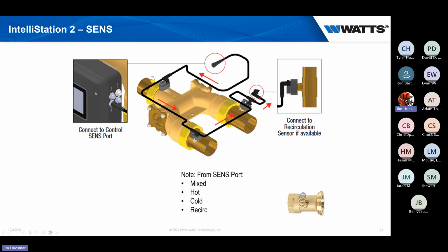What's also nice is now we have just 3, and we'll have 1 for the return, so just 4. But normally when we have 4, we'd have to consider that 8, because normally 1 is temperature and 1 is pressure. So they've redesigned this so each sensor covers pressure and temperature together. That way we can really cut down on the amount of sensors and the amount of wires rolling into this.